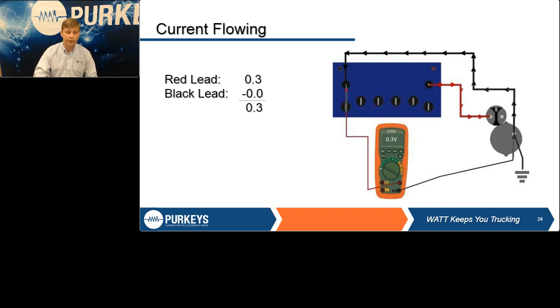Well, the answer is you don't know. And why don't we know? Because we have no idea how many amps that starter's pulling. So to do it this way is not a fair test. That's why the automated equipment's out there, so it puts a load on it to simulate it and knows what that load is and does all the calculations, tells you pass or fail. But that's exactly what that tester's doing when it does the test.